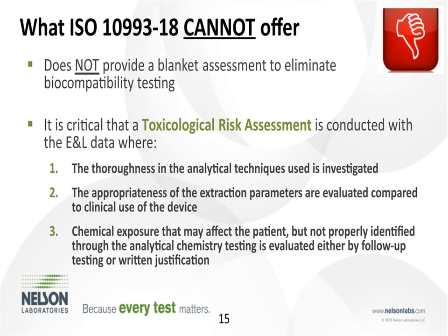Now, what it cannot offer: with extractable leachable testing, you cannot take your data, the numbers that come off the instrument, and use it as a blanket assessment to eliminate biocompatibility testing. You really need to do a toxicological risk assessment. This is where you make sure that the thoroughness of the analytical techniques that were used was appropriate, also that the extraction conditions used were appropriate, and that there may be a need for some follow-up testing. Say a compound is released in an unsafe amount. Follow-up testing may be needed, or a written justification as to why that amount may not be clinically relevant needs to be performed.